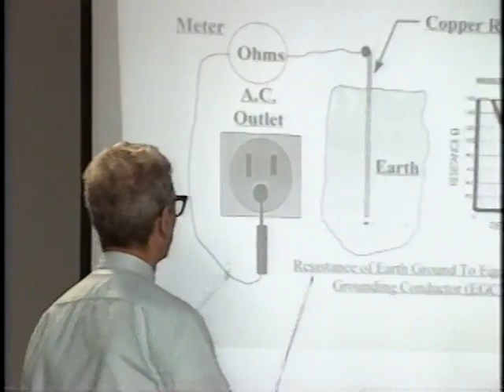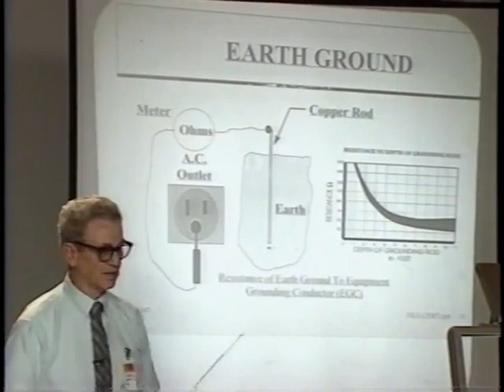Many people believe that you need an earth ground at every station. That is not necessary. A grounding rod has resistance, as you see from this chart. It is not 0 ohms to ground. The grounding resistance depends on the length of the rod, moisture, and other factors. What we do at a workstation is we use the third wire ground as the ground point to establish the equal potential at the workstation, and this is connected back through earth where the power company supplies the incoming power at the building.